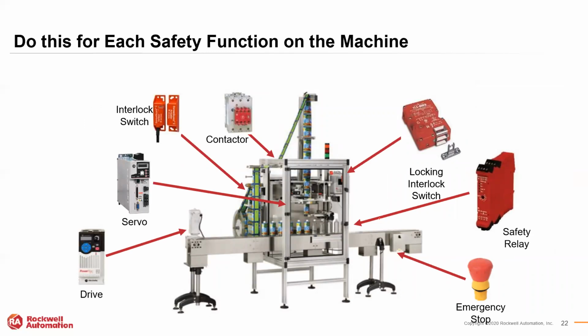So in other words, the whole machine is not necessarily PLD or SIL 2, but each safety function, such as open a guard door, shut off a servo, press an emergency stop button, shut off a VFD. So each safety function would be assessed and verified by that method.